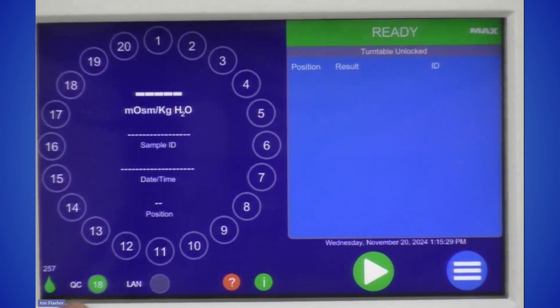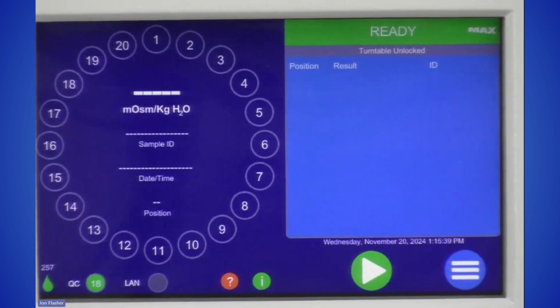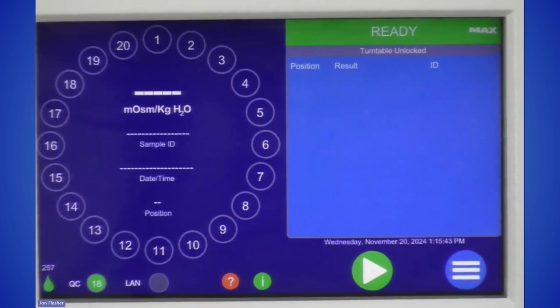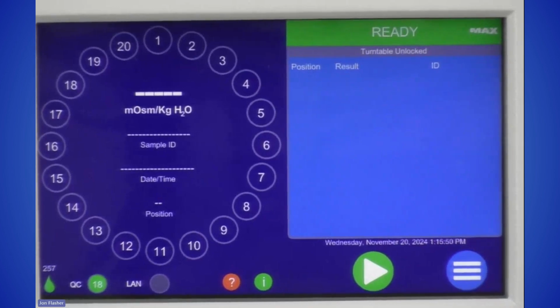This little QC indicator here is green when your QC has been performed and has passed for the day. The number within the QC indicator represents how many hours you have left before performing QC testing again. So that's that Clinitrol 290 standard that you have to run every 24 hours. Once that counts down to the time that you set, you'll have to run that Clinitrol 290 again before performing any testing for the rest of the day. So that is a gate to performing testing.